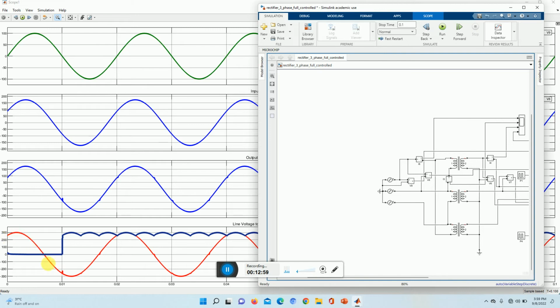So this red line we are getting is 300 volts. To summarize: input phase peak is 100, input line voltage is 173, the transformer secondary phase voltage is also 173 with no phase change, but the secondary line voltage shows a further 30 degree phase shift, so the original 30 degrees becomes 60 degrees total. So there is a 60 degree phase change overall. That covers these four voltage waveforms: the green, the two blues, and the red one.